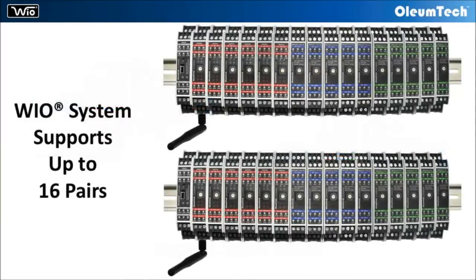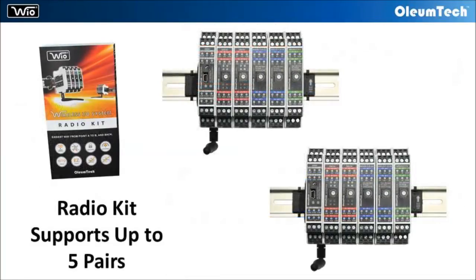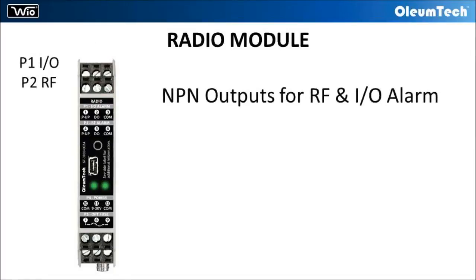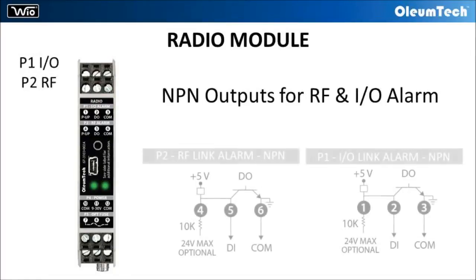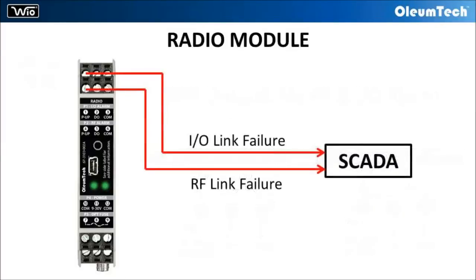Up to 16 pairs of modules can be operated on a single WIO System. The data rail supplied with the radio kit supports up to 5 pairs of I/O modules. The radio module provides 2 NPN outputs in the event of RF link failure or I/O link failure.